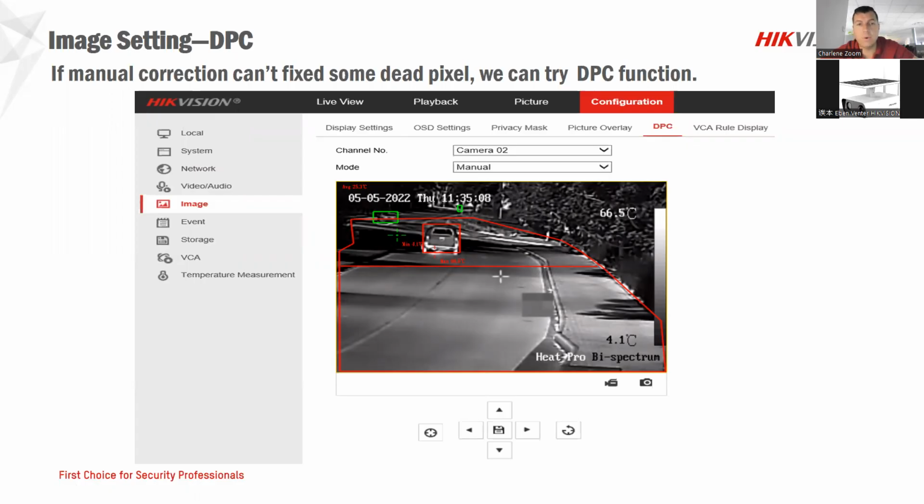So it gets sent to your ND, or it gets sent to Hikvision here by us, and our main person in charge of that will do the calibration itself. When we do the calibration, we have a little box. It's actually blue, but it's got a little black square block on it. Then we heat it up to, let's say, 40 degrees only. Then we set those devices to keep on detecting to make sure it's on 40 degrees, 40 degrees, 40 degrees. So we calibrate them according to that.